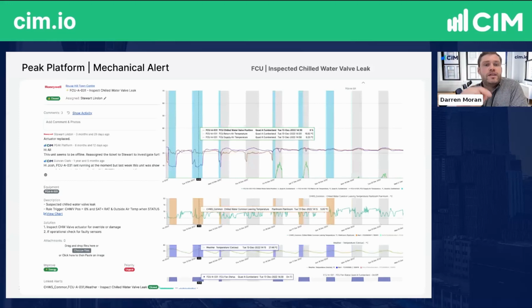If we click View Charts at the bottom of the screen, we can take a deep dive into the data. Here you can clearly see that the valve position at the top of the fan coil unit is at 0%, but the fan coil unit supply temperature is at 9.23. So we clearly have an issue here with the valve passing chilled water, especially when you can see that the outside temperature is at 27.5 degrees.